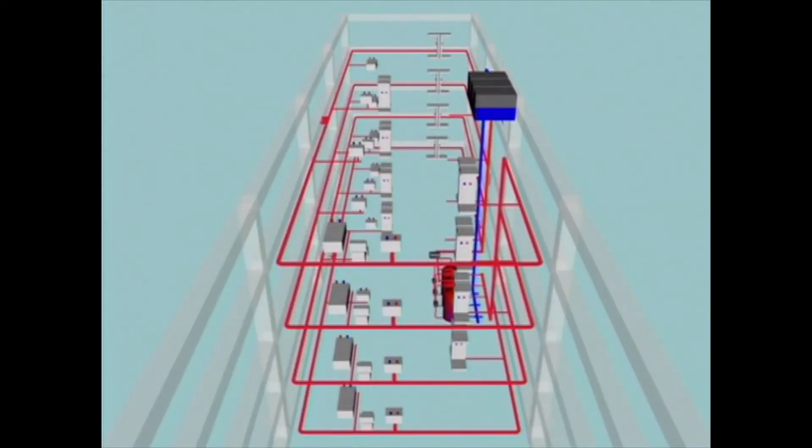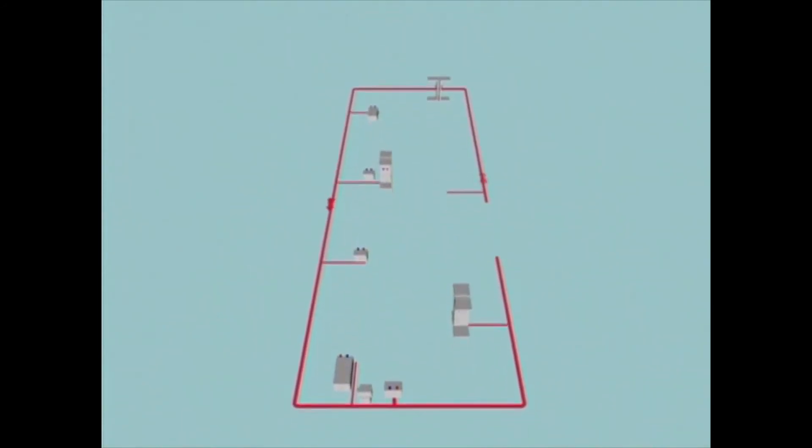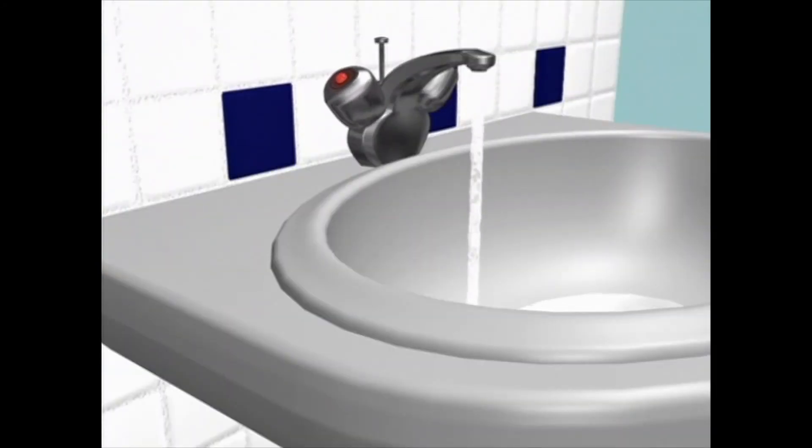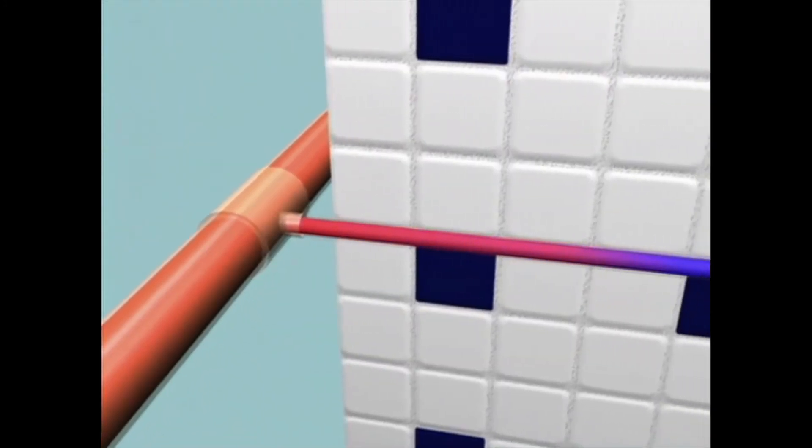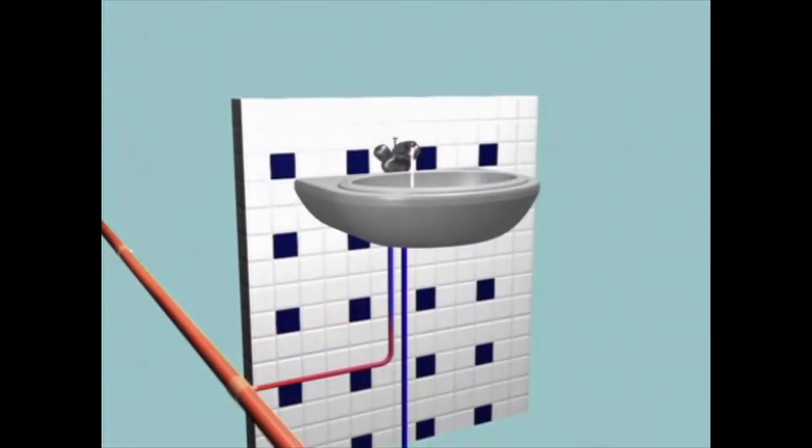There will usually be one loop of the ring main for each floor of the building, with outlets taken off it at various points. The advantage of this system is that when an outlet is turned on, the hot water only has to travel a relatively short distance from the ring main to the fitting. So hot water is available quickly and it is much easier to achieve the control temperatures at the outlet.